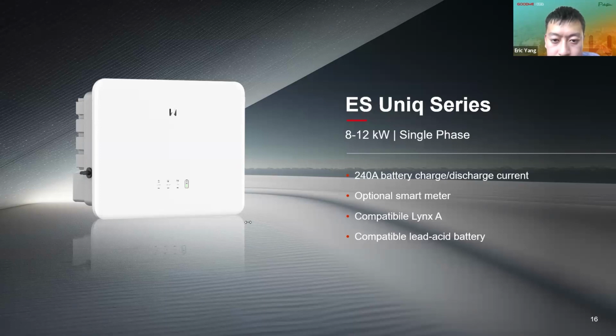Okay, we can see there are a lot of questions in the chat box. Is there any particular feature to run normal load and heavy load separately over PV in case of grid outage? We can set the protection point of the grid voltage of the inverter. That means if there is PV production, the grid voltage may increase because of the PV output. But if the customer has load, the grid voltage does not increase because the load will consume this PV production. And also if the grid voltage increases, we can set a different protection point of the inverter to make sure the inverter keeps working.